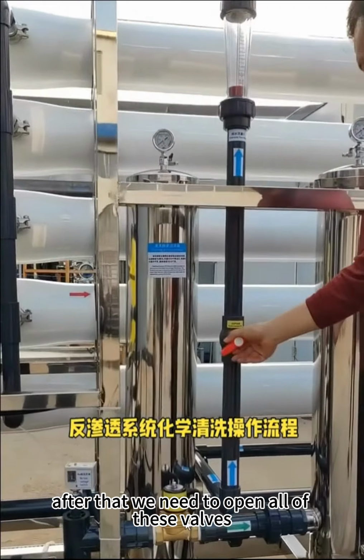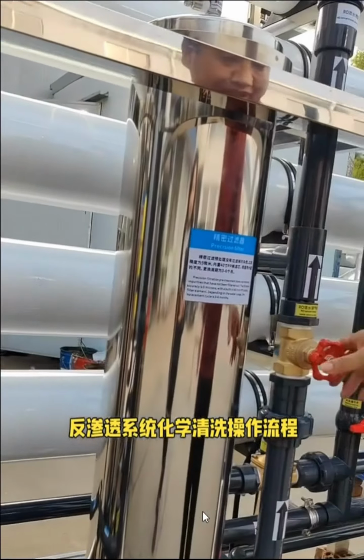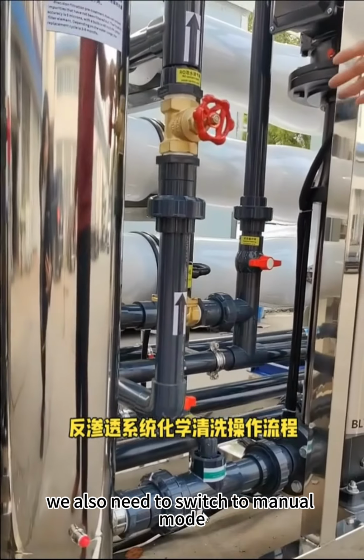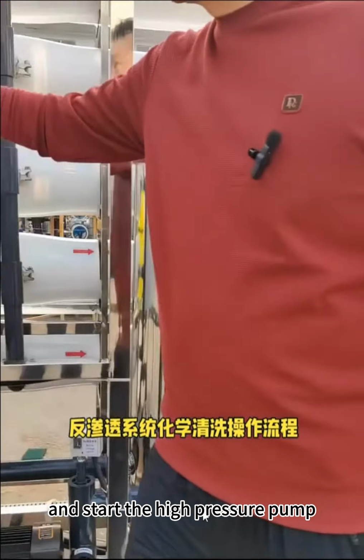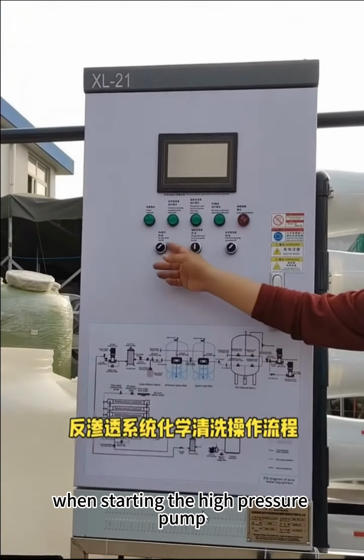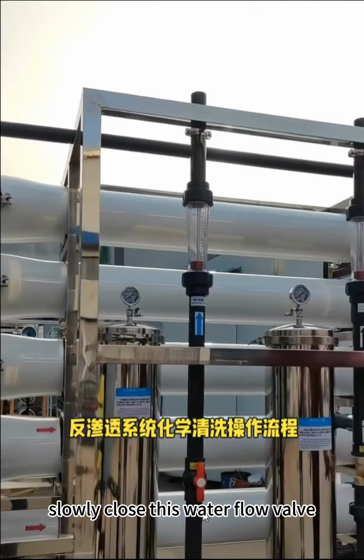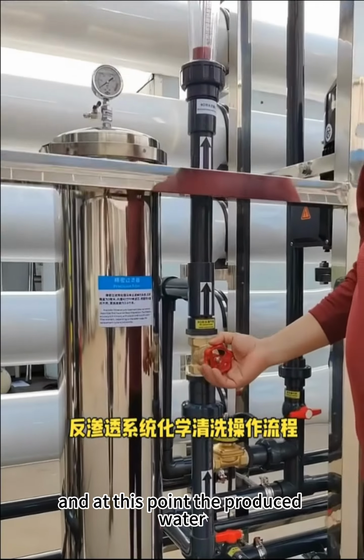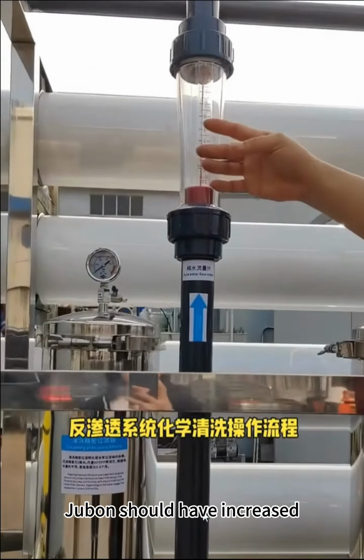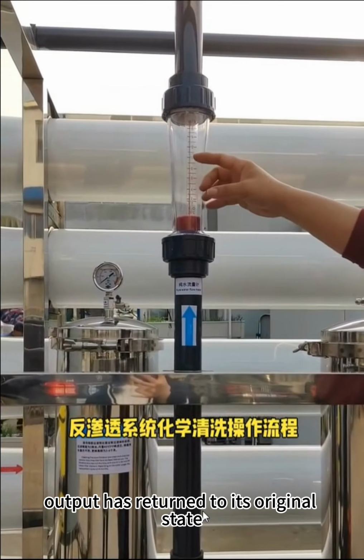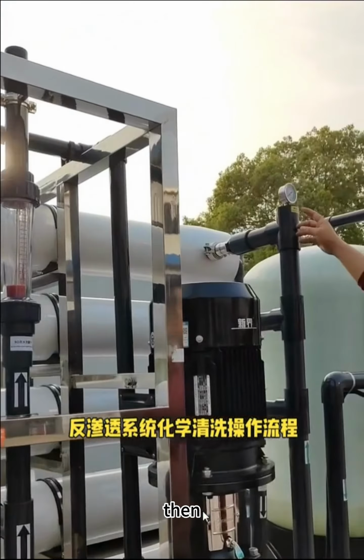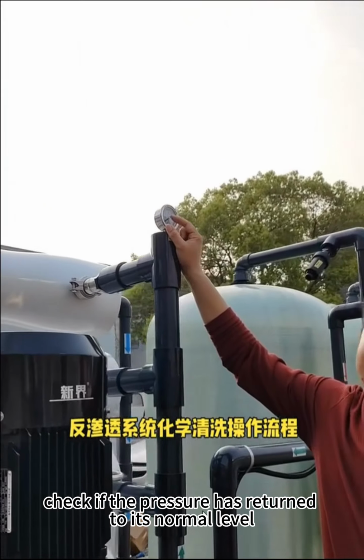After that, we need to open all of these valves. We also need to switch to manual mode and start the high pressure pump. When starting the high pressure pump, slowly close this water flow valve, and at this point, the produced water should have increased. So check if the water output has returned to its original state. Then check if the pressure has returned to its normal level.